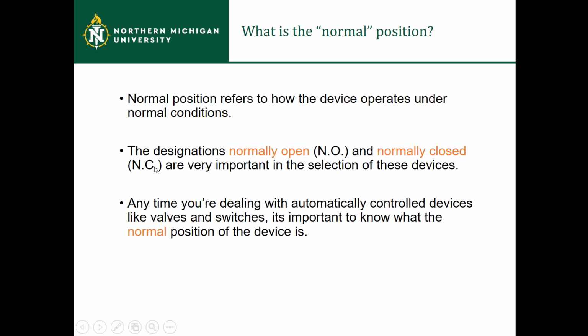At this point, it's important to understand what normal position means. Normal position refers to however that device operates under normal conditions, whether it's supposed to be normally open or normally closed. So it's important to note whether it's an NO or NC type function. If you see something in normal operation that's supposed to be open but it's actually closed, then we understand there's an issue with the system.